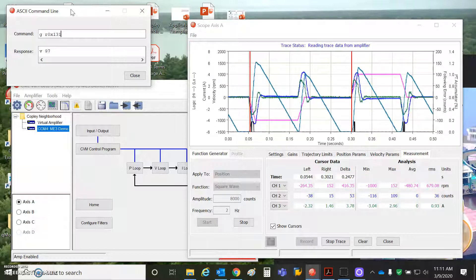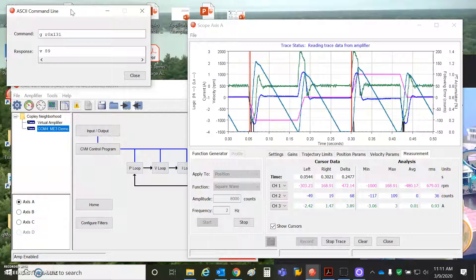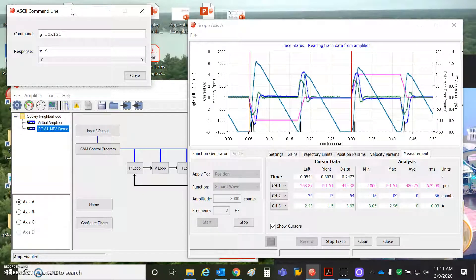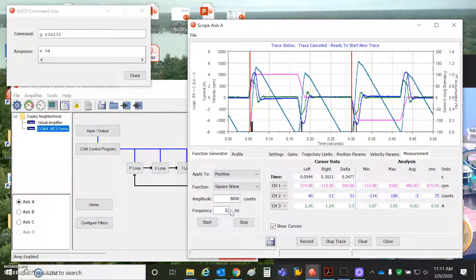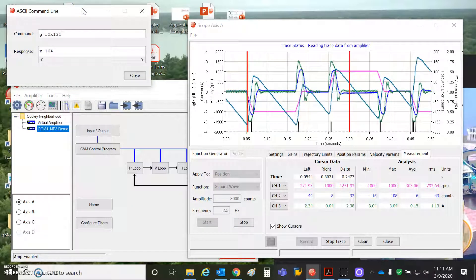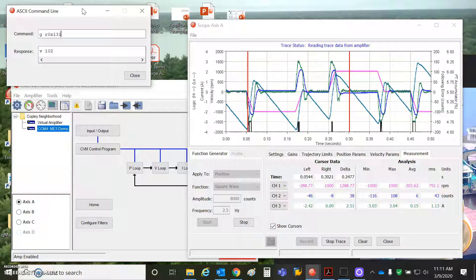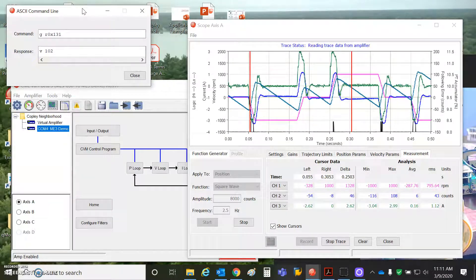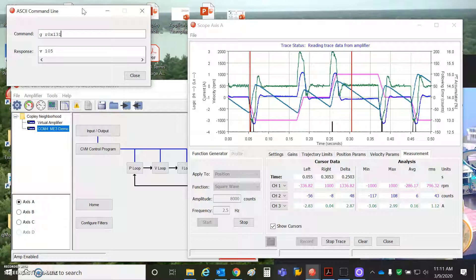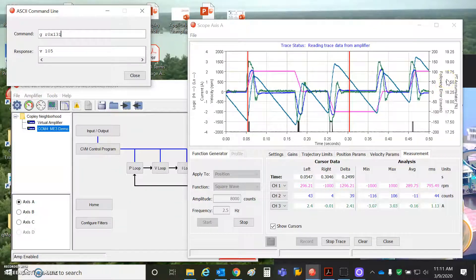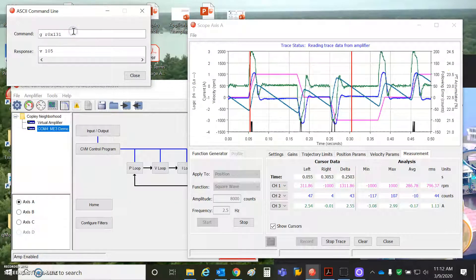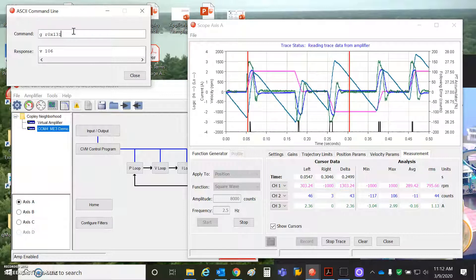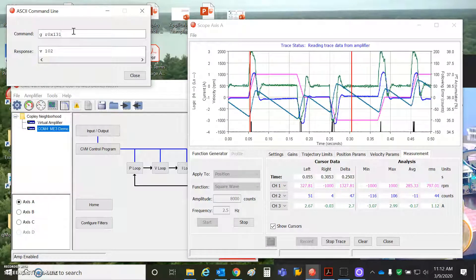So we can see with this higher duty cycle, we're approaching the one amp. As I read this periodically, less than once every four seconds, I have an RMS current that says I can do this all day. If I increase this frequency, you'll notice that the RMS current will start to grow. And this is the danger zone. When you're above the one amp, you're going to start accumulating your I squared T limit. And then eventually you're going to get a following error and something bad is going to happen. I'm only at 20 percent. I got plenty of time before I have a problem. But I should take corrective action and reduce my cycling because this is the danger zone here.